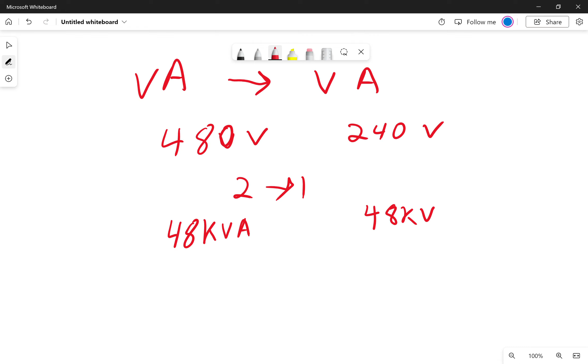So if I told you that on the primary side we had 48 kVA, and asked how many amps, what's the amperage draw on the secondary side? Well, the voltamps will be the same, so we just do the math. We take our 48,000 voltamps, kVA meaning 1,000 voltamps, divide that by 240 volts. Our volts cancel, and 48,000 divided by 240 gives us 200 amps. So that's a 200 amp service.